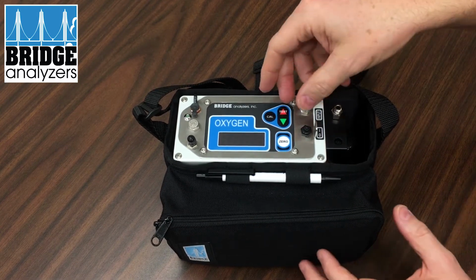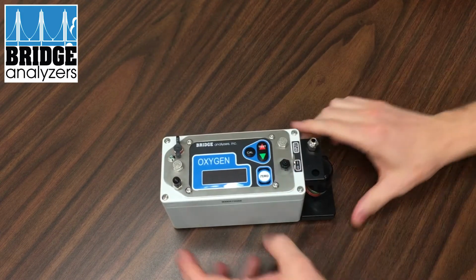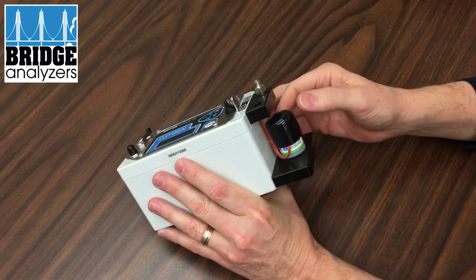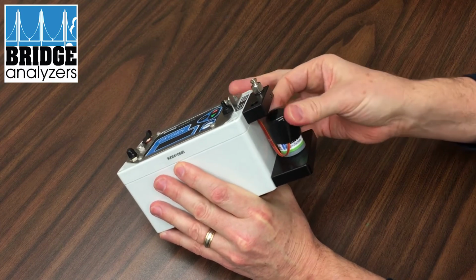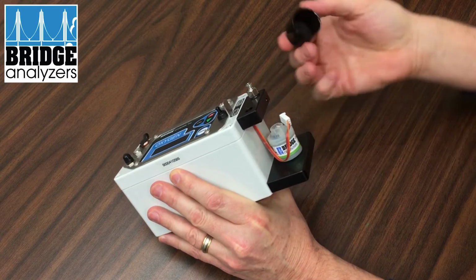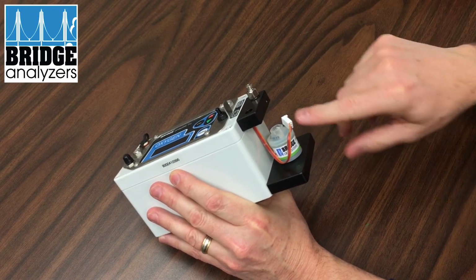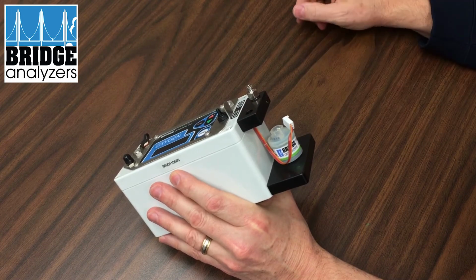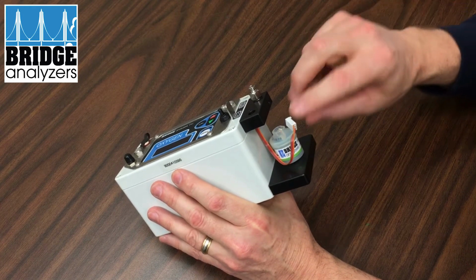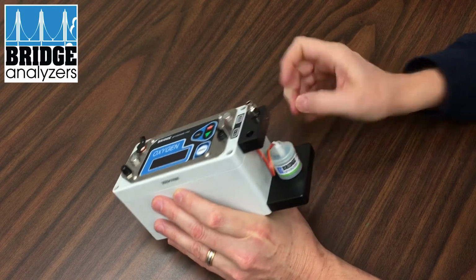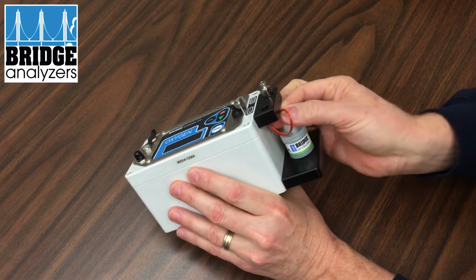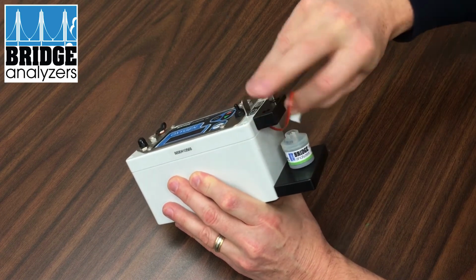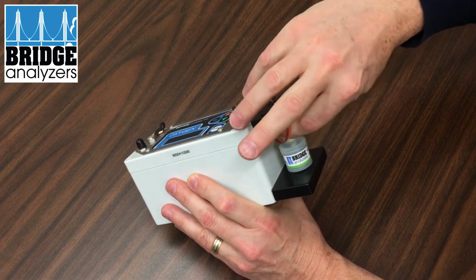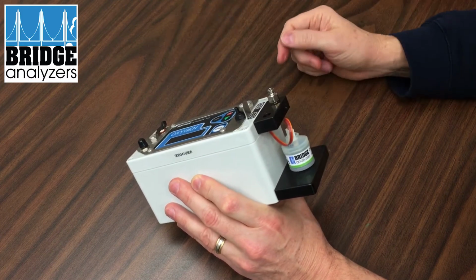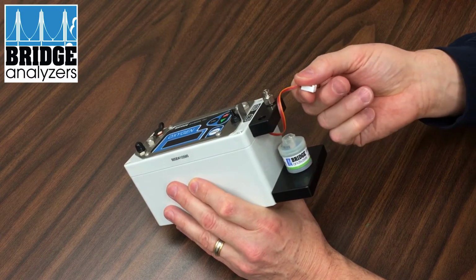So what you would do is remove the analyzer from the case, which then exposes the oxygen sensor. You remove the black cap. In this case, I had the connector off so that you would see the off on the display, but normally it would be connected here, like so. You can actually remove the connector and plug it back in and then try to see if the off goes away, because in some cases you may have just had a bad connection.